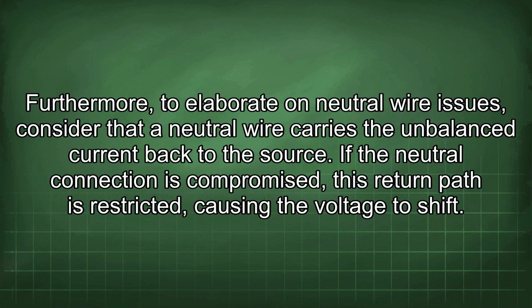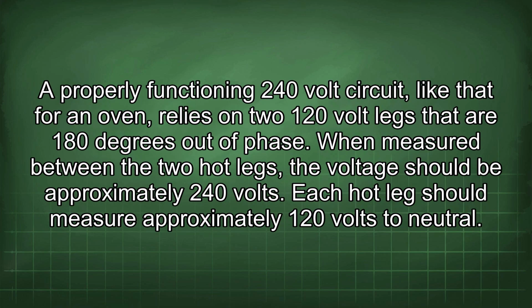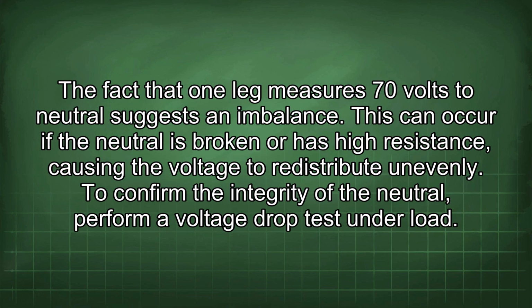Furthermore, to elaborate on neutral wire issues, consider that a neutral wire carries the unbalanced current back to the source. If the neutral connection is compromised, this return path is restricted, causing the voltage to shift. A properly functioning 240-volt circuit, like that for an oven, relies on two 120-volt legs that are 180 degrees out of phase. When measured between the two hot legs, the voltage should be approximately 240 volts. Each hot leg should measure approximately 120 volts to neutral. The fact that one leg measures 70 volts to neutral suggests an imbalance. This can occur if the neutral is broken or has high resistance, causing the voltage to redistribute unevenly.